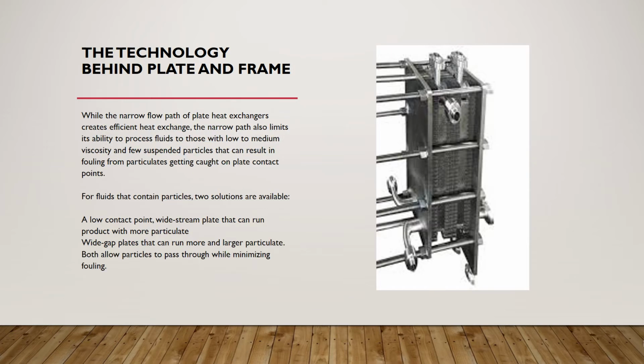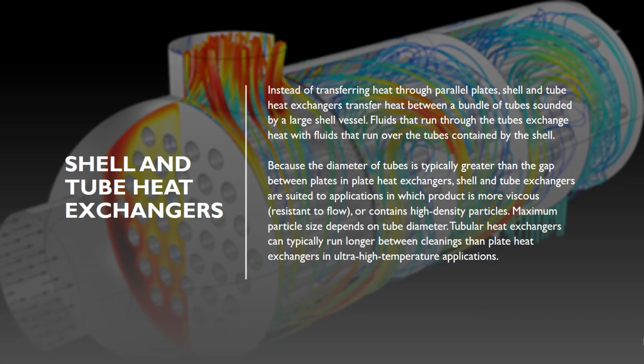While the narrow flow path of the plate heat exchangers creates efficient heat exchange, the narrow path also limits its ability to process fluid to those with low to medium viscosity and few suspended particles that can result in fouling from particles getting caught on the plate contact points. For fluids that contain particles, two solutions are available. A low contact point, wide stream plate that can run product with more particles. Wide gap plates that can run more and larger particulate. Both allow particles to pass through while minimizing fouling.